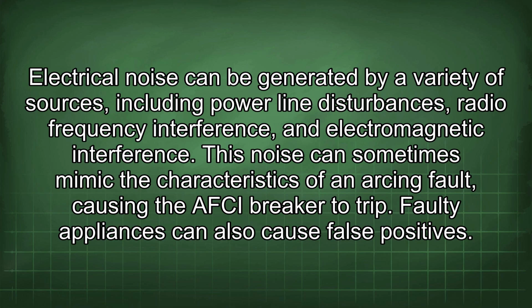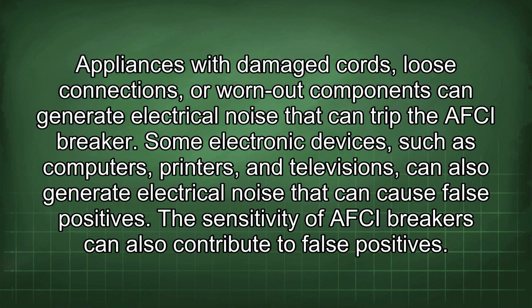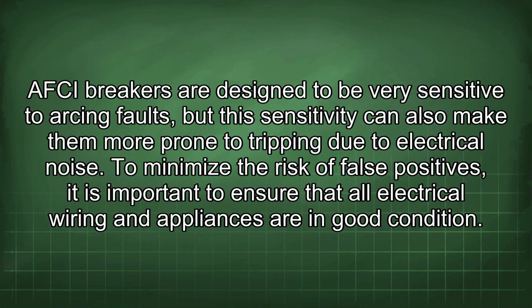Faulty appliances can also cause false positives. Appliances with damaged cords, loose connections, or worn-out components can generate electrical noise that can trip the AFCI breaker. Some electronic devices, such as computers, printers, and televisions, can also generate electrical noise that can cause false positives. The sensitivity of AFCI breakers can also contribute to false positives. AFCI breakers are designed to be very sensitive to arcing faults, but this sensitivity can also make them more prone to tripping due to electrical noise.